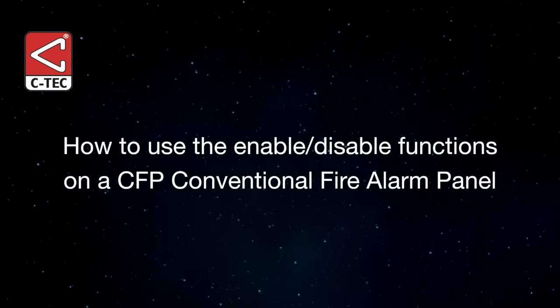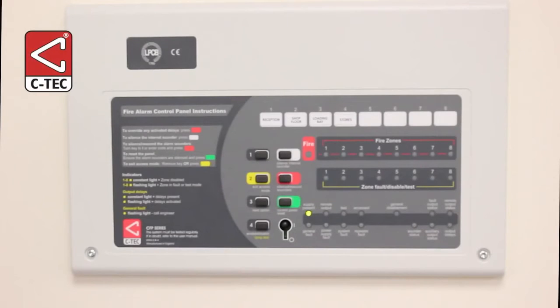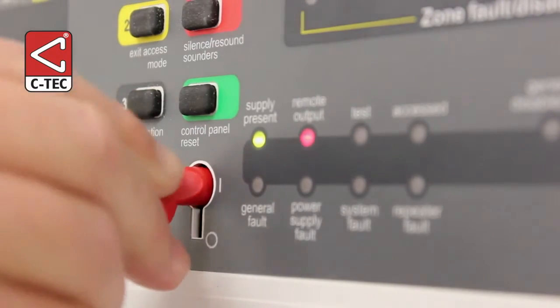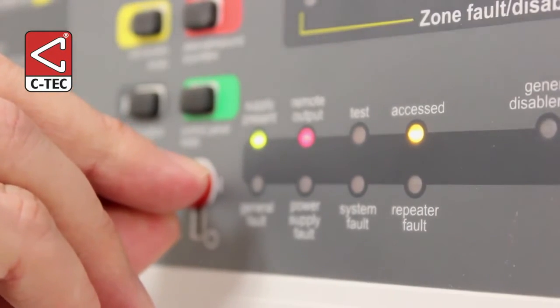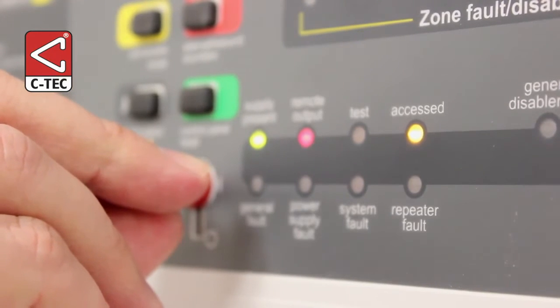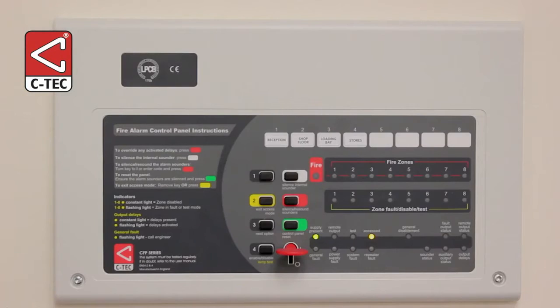Access to these controls, you must first put the panel into access level 2. You can do this using one of two methods: entering a secure code using the panel's keypad or turning the key switch. The access light will turn on to indicate the authorised user controls are operative. You can enable and disable functions you require using a simple selection process.